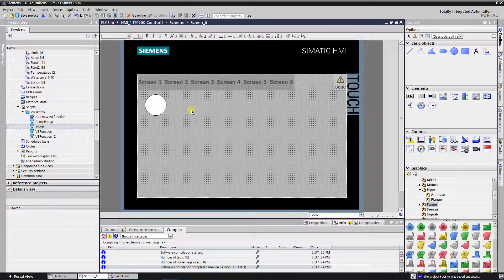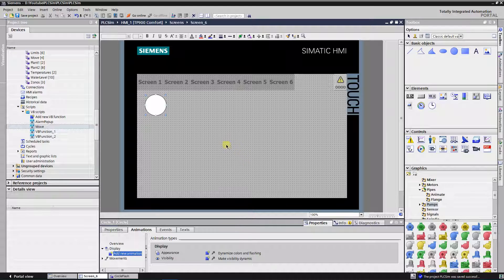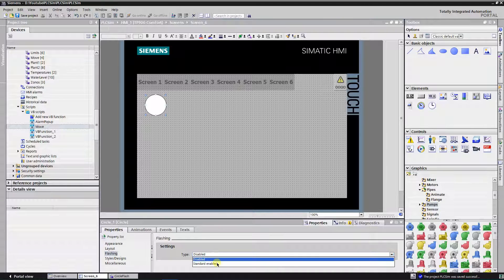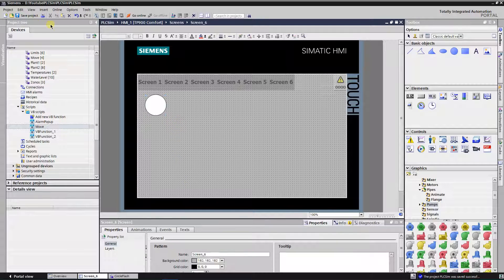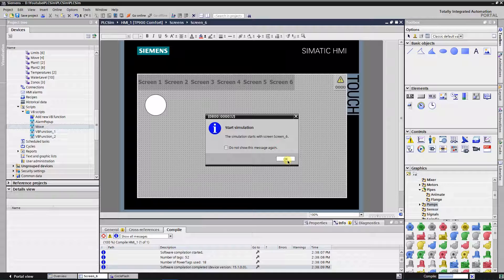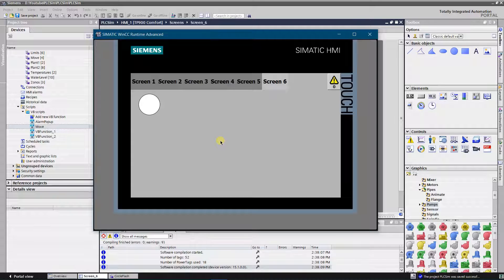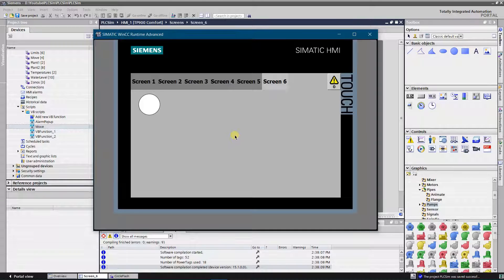Let's add a simple animation called flashing. Select your shape, find flashing from the property list and select standard enabled type of flashing. Let's test it. Now we have a flashing shape. The flashing property is based on swapping the color of the fill of the background with the color of the border on regular intervals. So the background of the shape changes between white and black, while the color of the border changes between black and white.